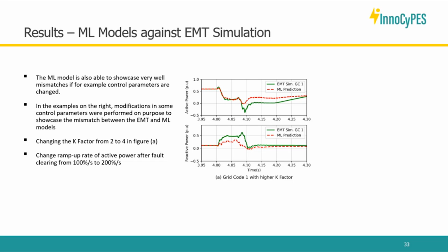Basically, I changed the K factor, which is the gain that the turbine should inject reactive power. So for a certain voltage drop, the reactive power should rise to a certain value. In the EMT model, I increased it to 4, and on the machine learning model, I kept it at 2, which is exactly what I wanted to see. I wanted to see the mismatch, because this is what we want to use these machine learning models for. We want to use them to see if we are being compliant, if we are following what we expect. So it's more or less finding a way of having a machine learning model that represents your expectations for a wind turbine in the field. And you want to check if those expectations are met. And this is what we see for the K factor.